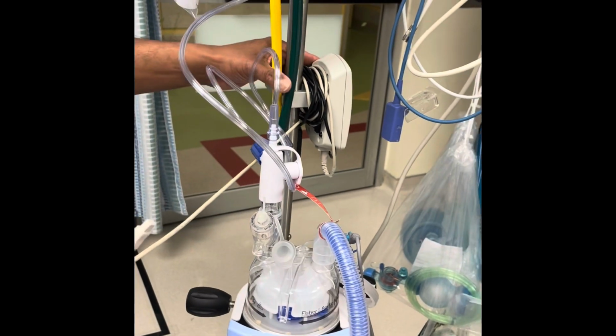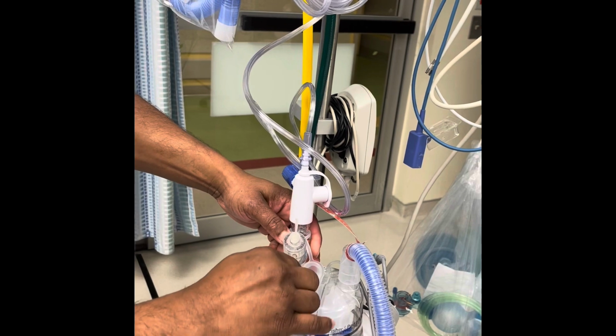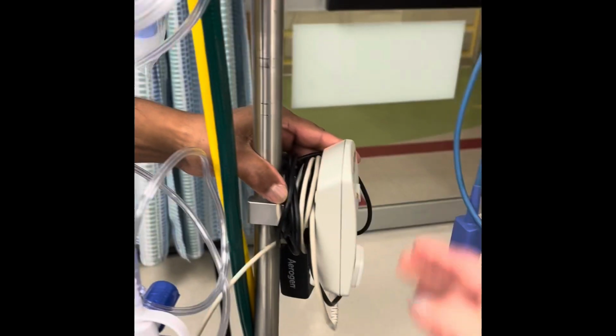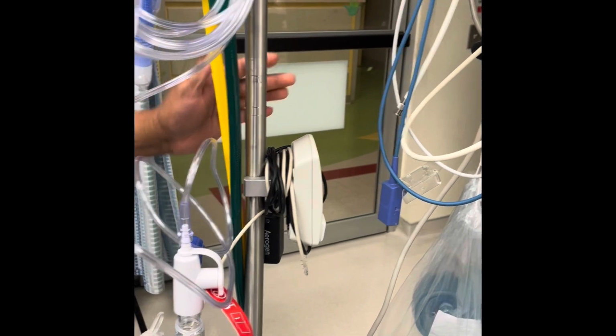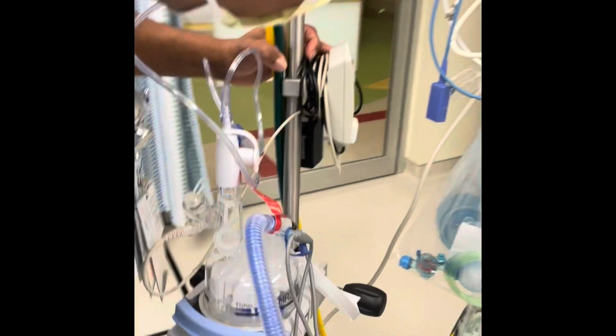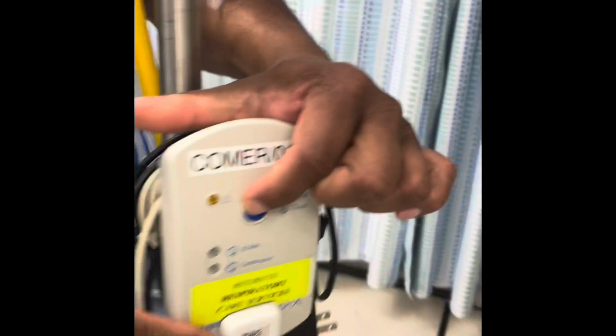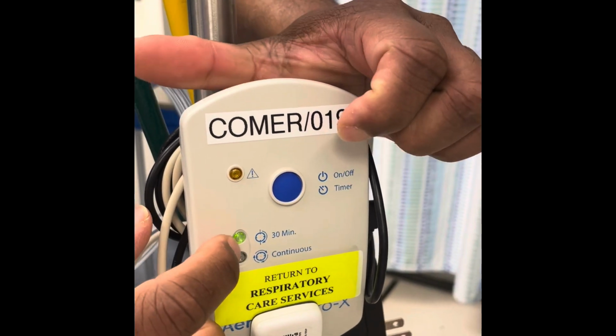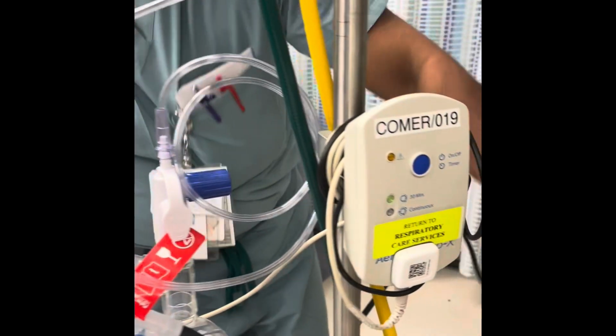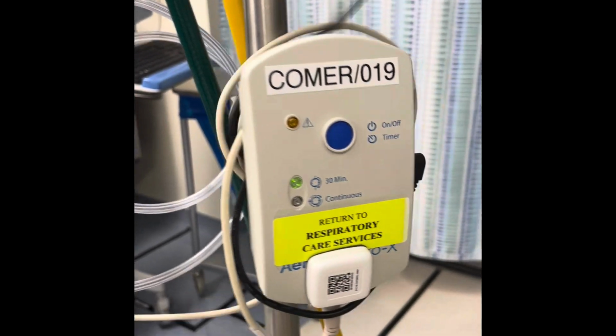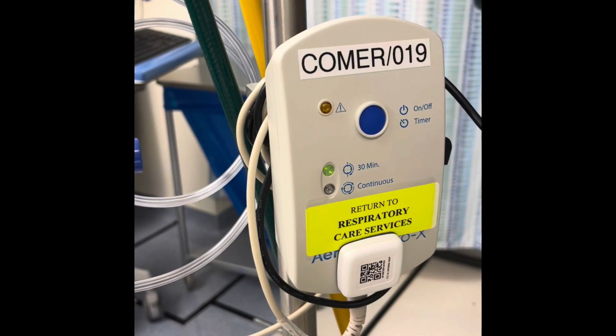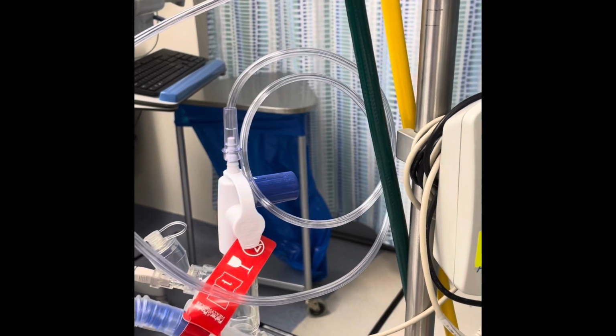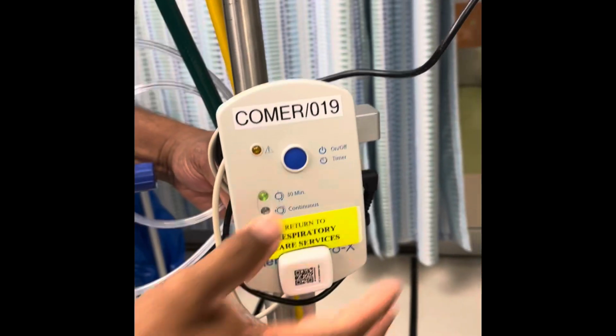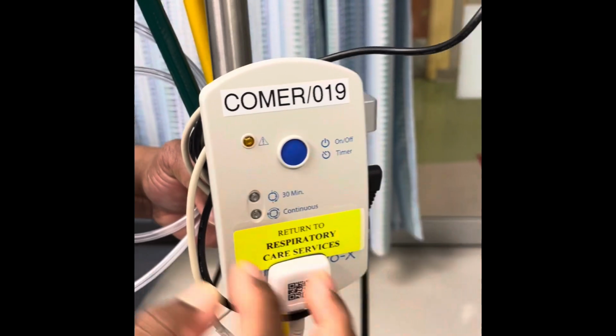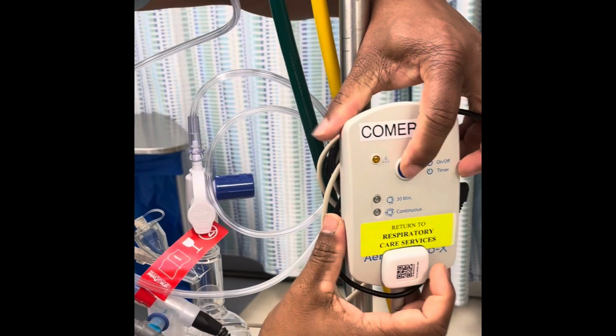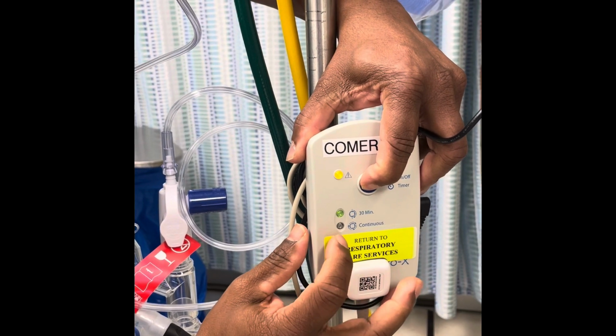Of course, the Aerogen needs to be connected to the patient. And does this come on all the high flow machines? Well, I will say about 90% of the high flows have that Aerogen in there. All we need to do is press the button on the side, and it will light up over here, though it's not plugged in. And it gives you the option for continuous versus intermittent. If it is just intermittent, then it will give you that. In case you need to go to continuous, just hold this and it will change.